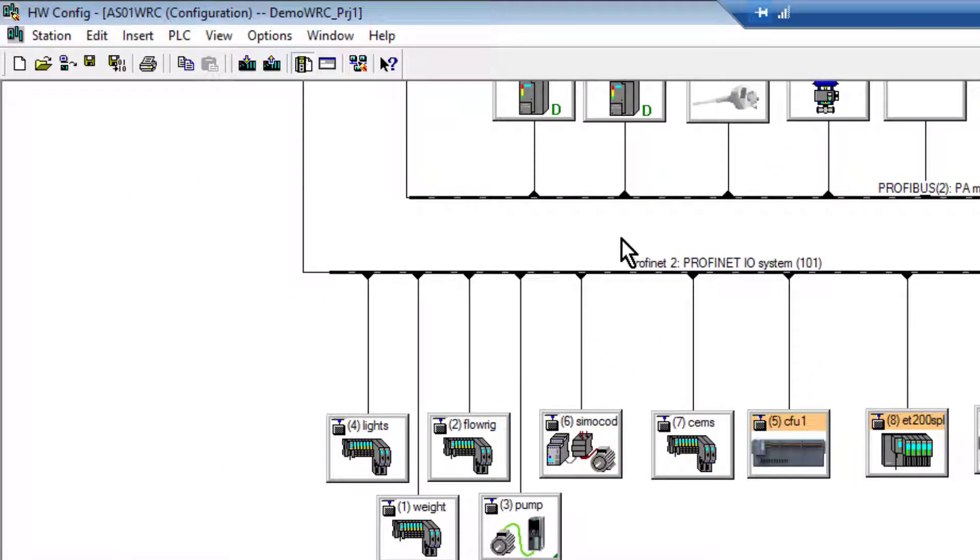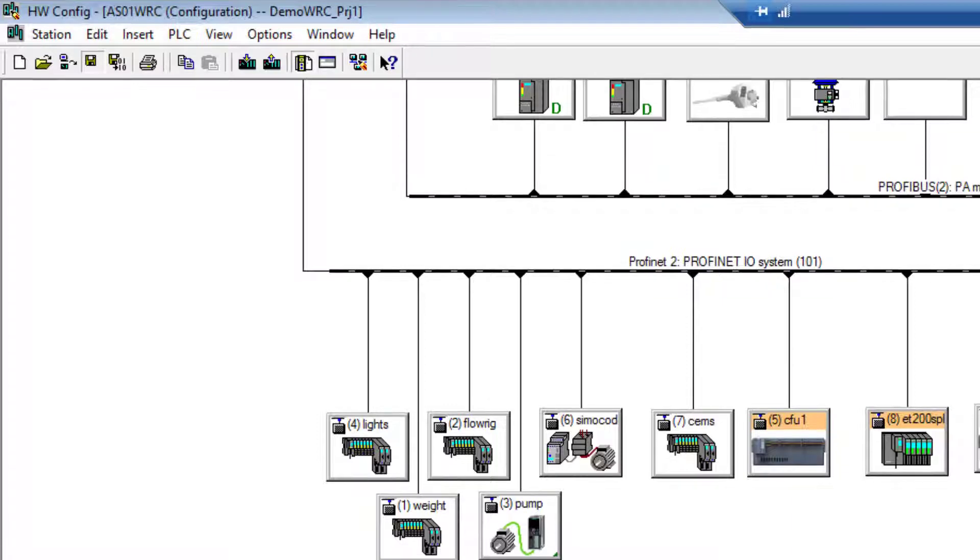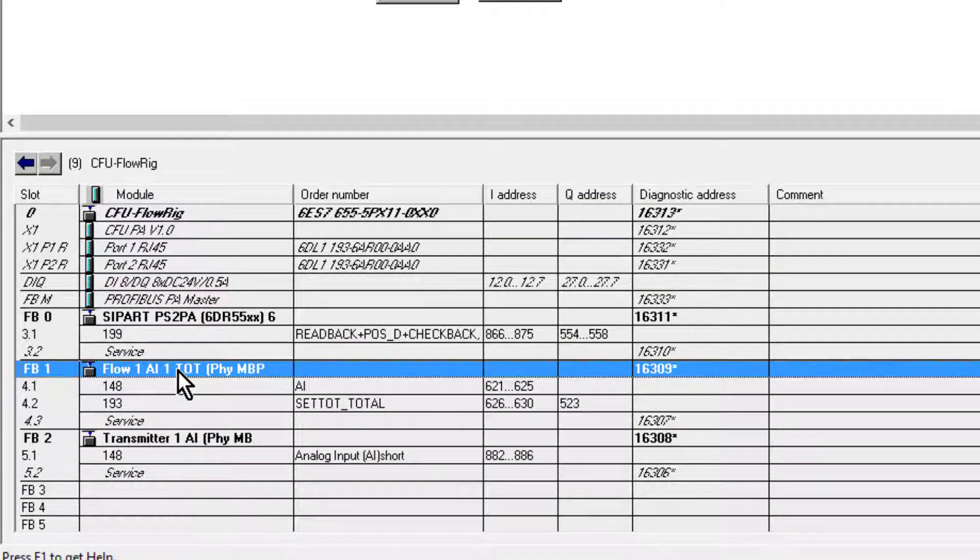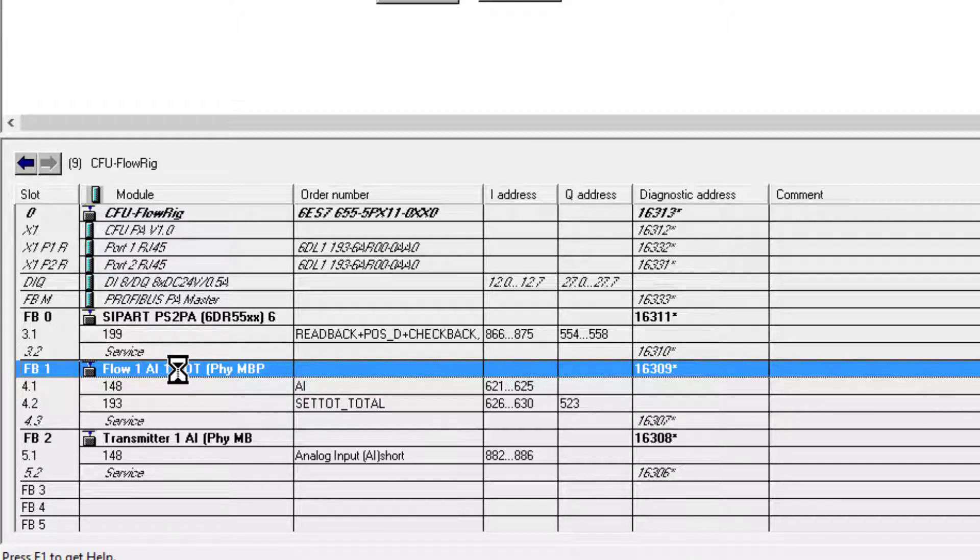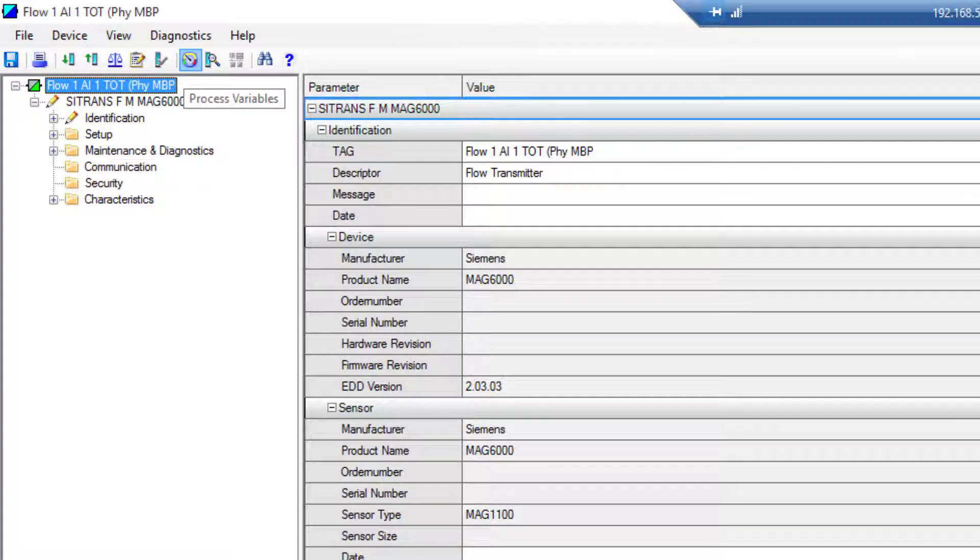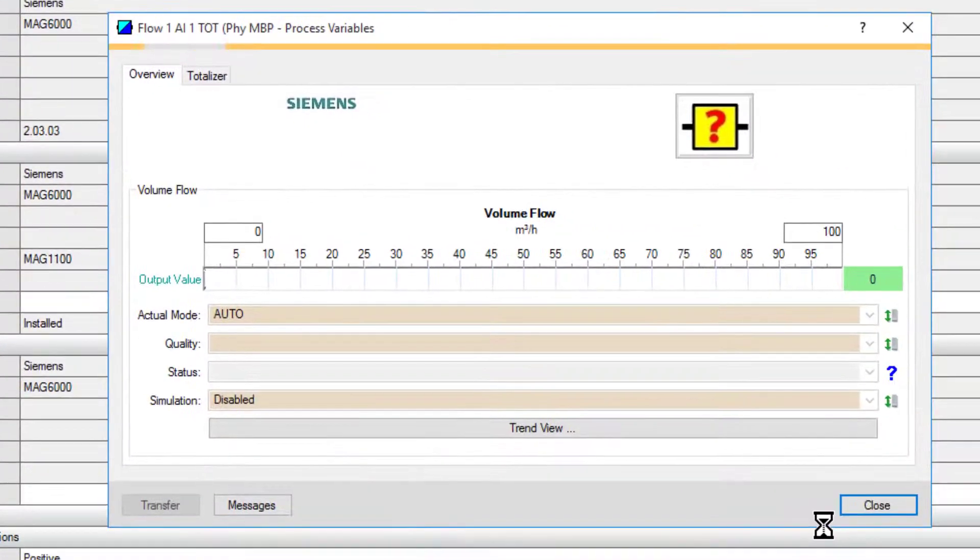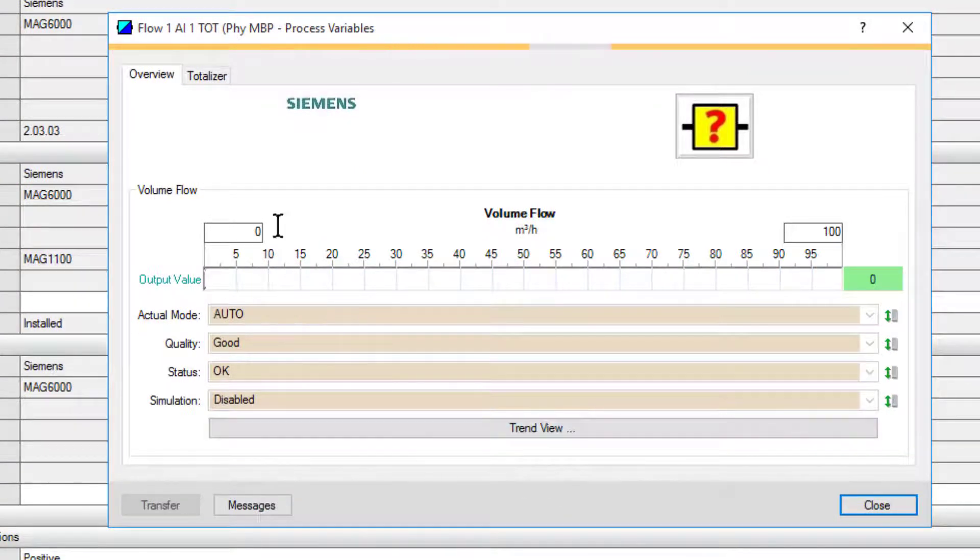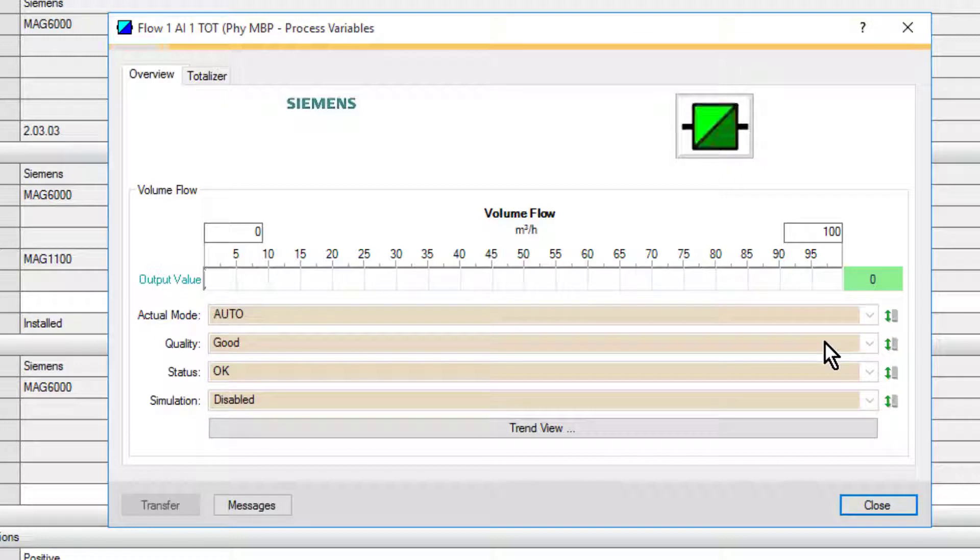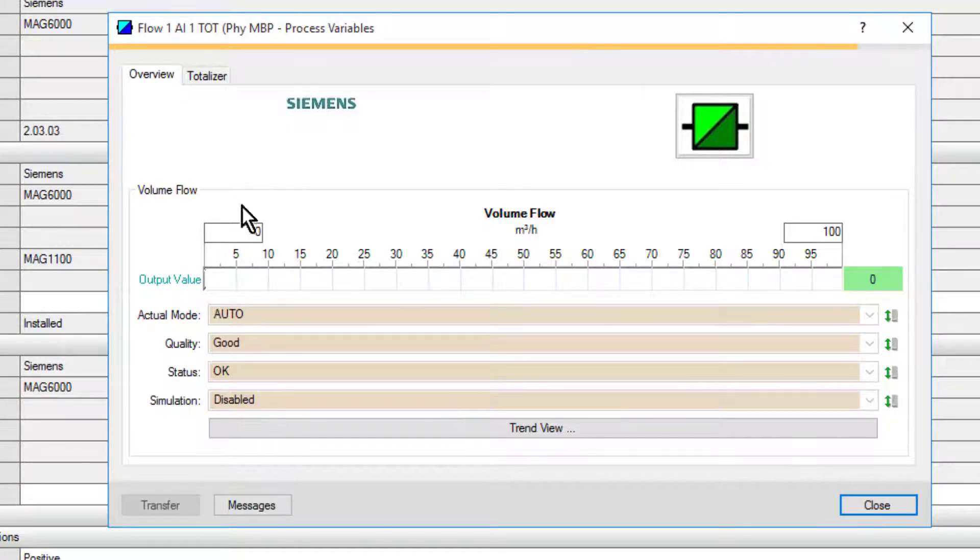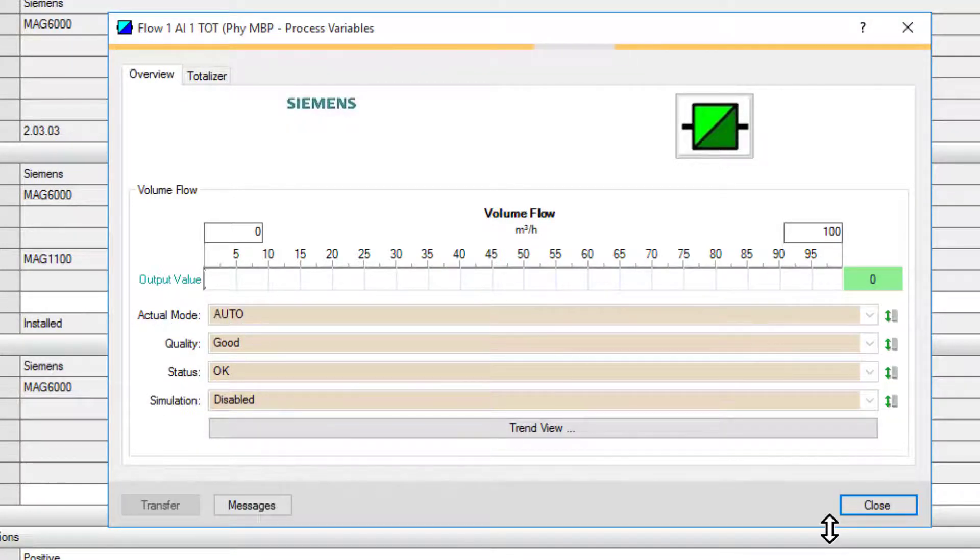I don't have to do a compile or a download, just save my project if I want to open up PDM. So double-click of that device, and then to go online I can just read the process values. I can see that it's online and everything is being updated quite nicely within my values. So healthy instrument, there's no flow at the moment, simulation is disabled, and the status is good.